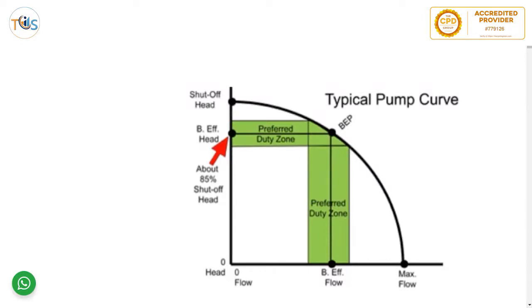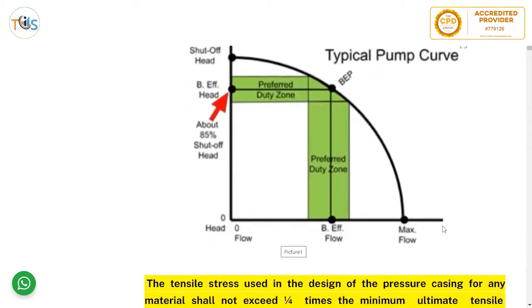On the pump curve, the horizontal axis is flow and the vertical axis shows head or pressure. There is a green zone that is the preferred operating range — below it you have cavitation and surge, and above this range you have chatter, vibration, and resonance. This green zone represents the best efficiency region.